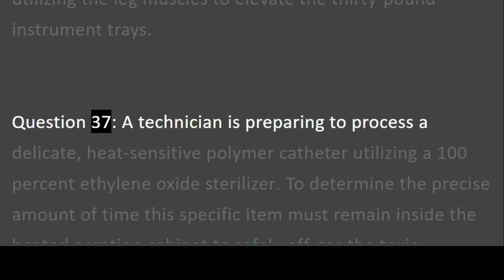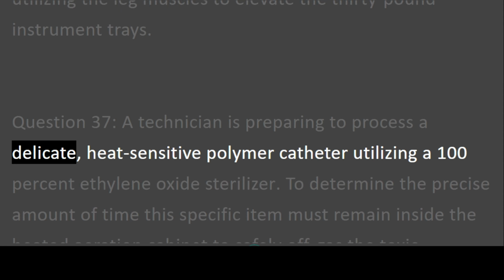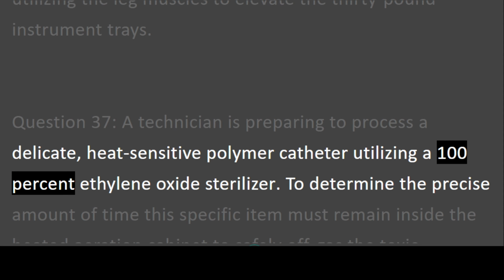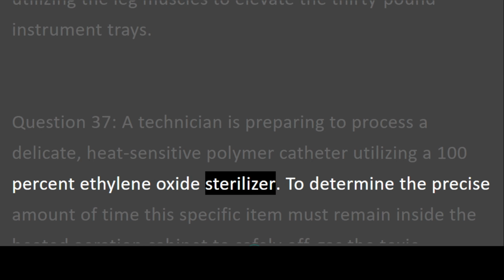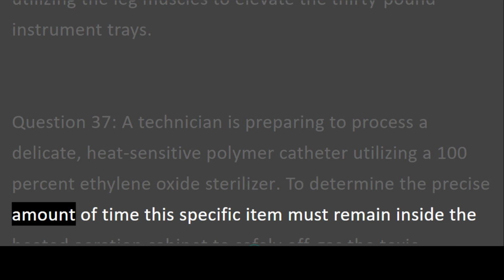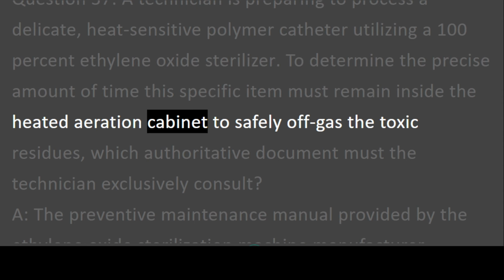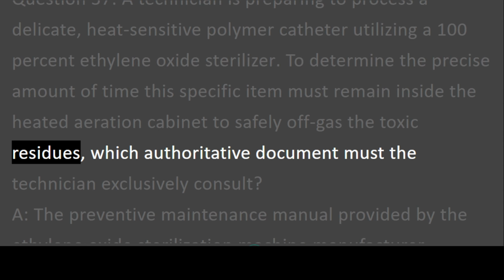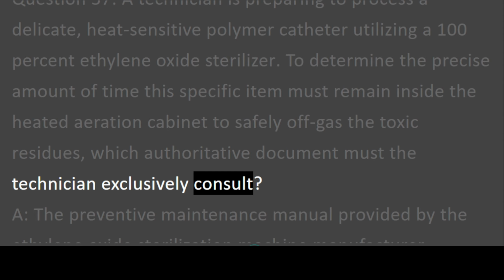Question 37. A technician is preparing to process a delicate, heat-sensitive polymer catheter utilizing a 100% ethylene oxide sterilizer. To determine the precise amount of time this specific item must remain inside the heated aeration cabinet to safely off-gas the toxic residues, which authoritative document must the technician exclusively consult?